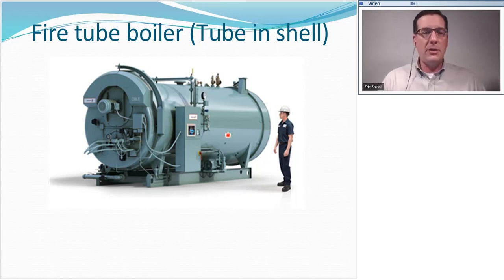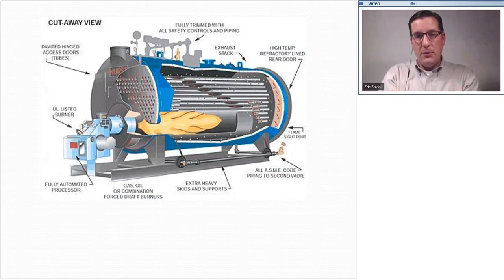Fire tube boilers consist of a metal shell, which is round, which is filled with water. They have a bunch of tubes running through that water space, carrying both the flame and the resulting products of combustion, and allowing the heat to transfer through the walls of those steel tubes into the water that is surrounding them. And of course, the water is circulating through, coming in one side and leaving the other.